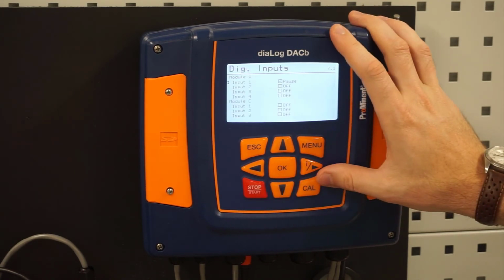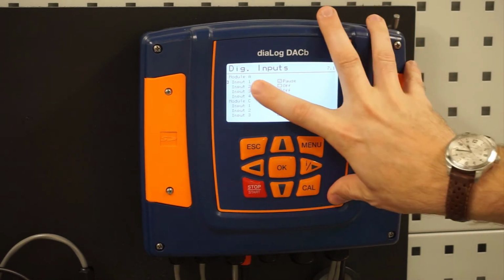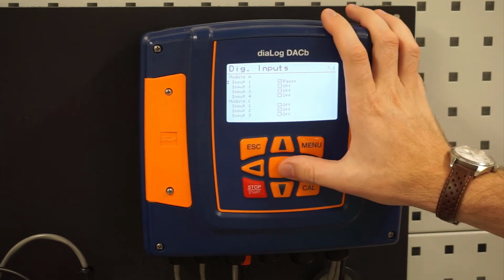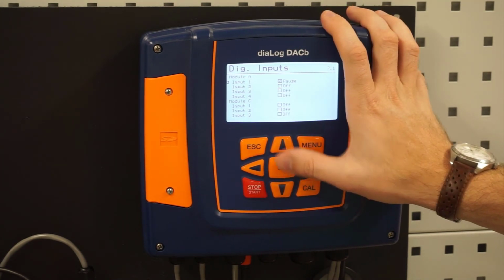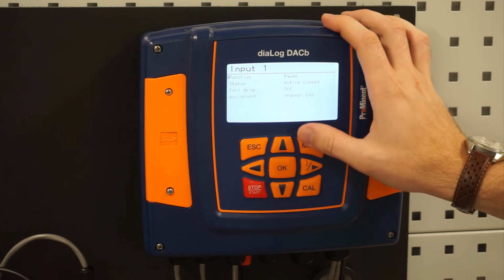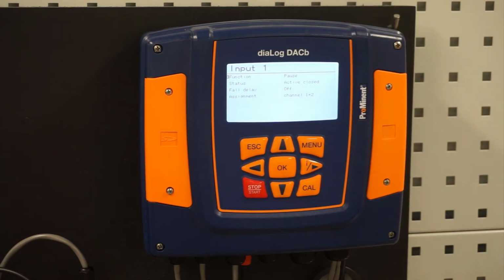Next is your digital input. In this case, our digital input 1. In most cases, if you buy a package from us, input 1 will be set up, and it is set up for our flow. So if we lose flow, it's going to pause our controller. That is for safety. When we pause the controller, if we have any type of control set up, it will stop that pump from running. So we're not feeding acid into a stagnant line of water.